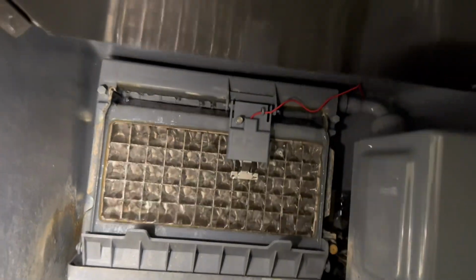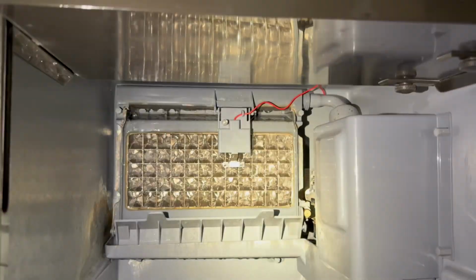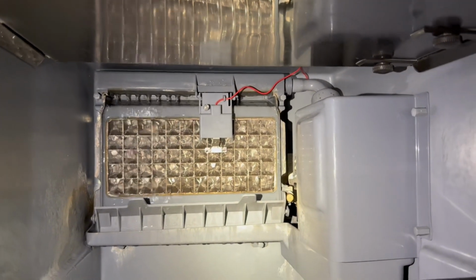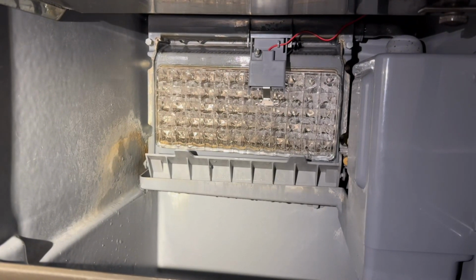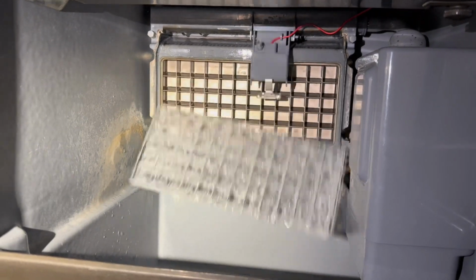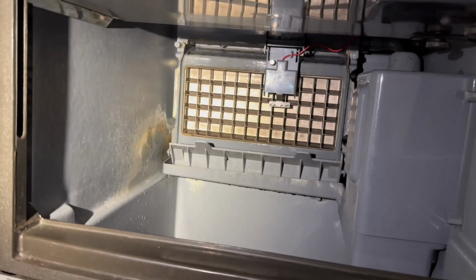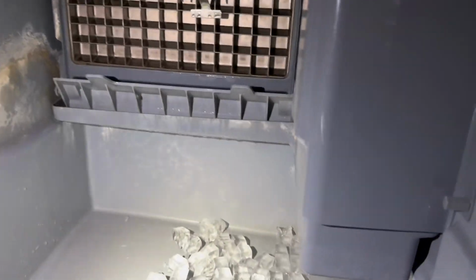There it is. Now we are in harvest, and we're gonna wait for this sheet of ice to drop. It's a really good harvest time. Call that about 1 minute and 9 seconds. Good solid sheet of ice down there. So that wraps up that service call on the Manitowoc QM45A. Was kind of unfortunate that I reset the machine.